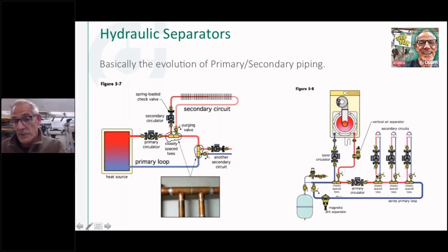So then, we talked about this a little bit last week, the downside with this series primary loop is every one of these is going to see a lower and lower temperature when they're all running. Let's say I'm coming in here at 160, coming back at 140, blending with that. You can see how the color of these lines changes as we go around the loop here. I see a lower temperature, lower temperature. So you had to know that. If you need the same temperature at the end of the road here, with this series primary loop, you're not going to get that. Think of it like the old Christmas tree bulbs. When you pull the first one in series out, the rest of them go out because you're broken in the series. That's one of the downsides of doing the series primary loop.